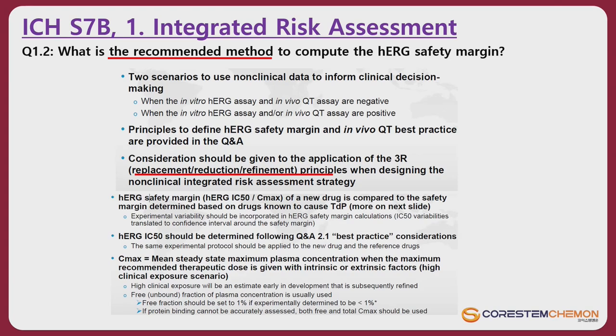For in vitro best practices: the recording temperature should be set between 35 to 37 degrees Celsius. The scientific literature from early 2000 shows that room temperature versus physiological temperature gives a 20 to 30% difference in hERG ion channel current. For the protocol, in the past each organization could use a different protocol, but now a standardized FDA-recommended protocol is published. Potassium current can be at minus 40 or minus 50 millivolts where it is inactivated, and this is now standardized.